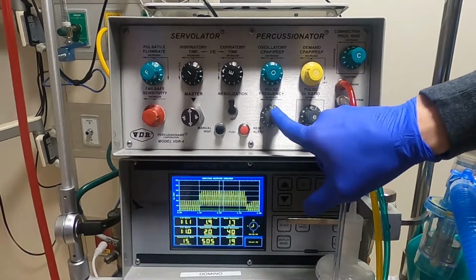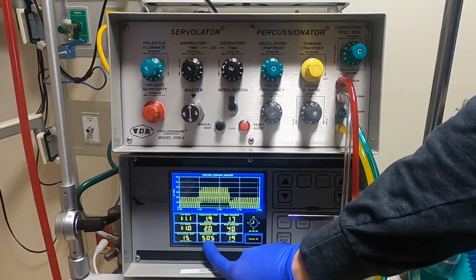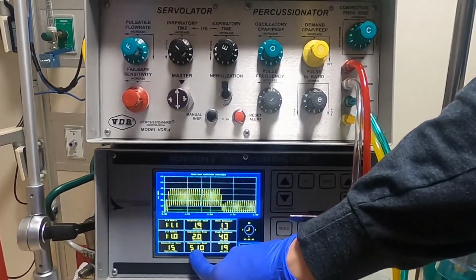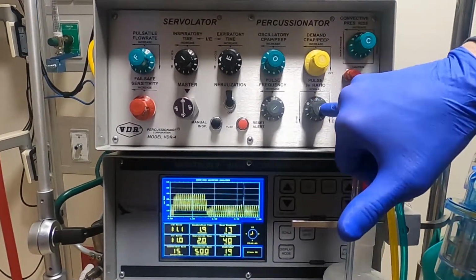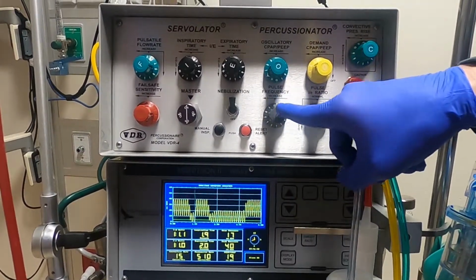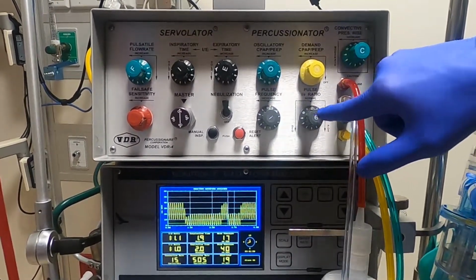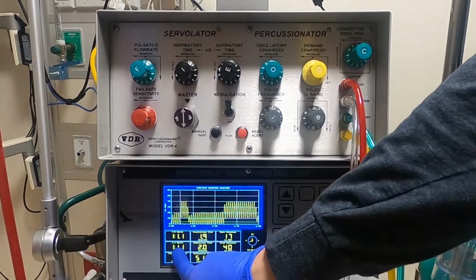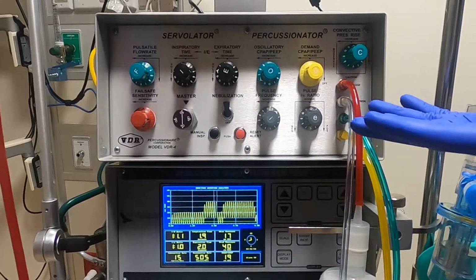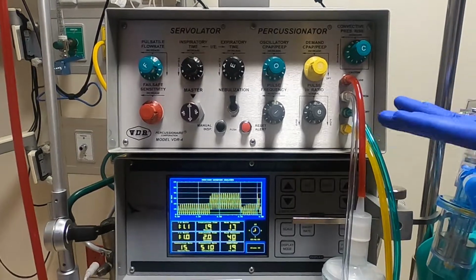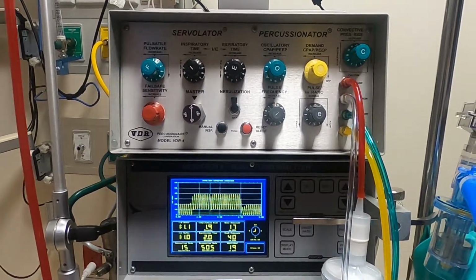Here we have our pulse frequency, which is our high frequency rate. And then our pulse IE ratio, which is basically the IE ratio of our high frequency breaths. Usually we'll leave that at 1-to-1. You can do some manipulations on that, depending on what's going on with the patient, but in general, we leave that where it is.